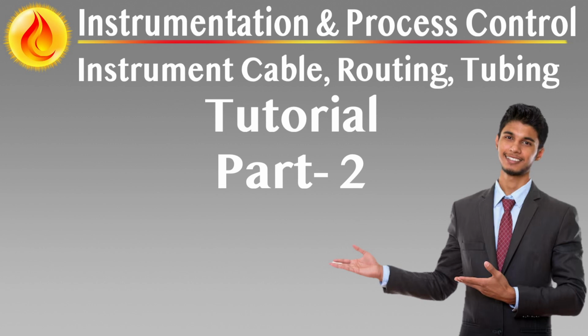To protect sensitive electronics, field wiring must not be connected to instruments until all welding activities in the area have been completed. Welding currents must not be permitted to flow through instrument ground paths or signal lines, as this can cause irreversible damage to internal components.